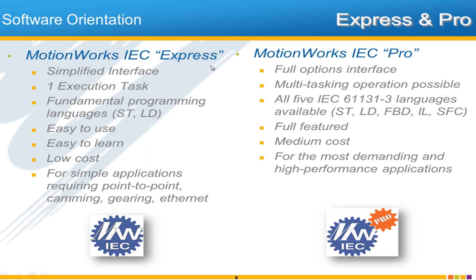The main limitation of Express is that it can only execute one task — we'll see what that means as we progress. With MotionWorks IEC Pro we have multitasking capability, which adds a performance advantage. Express also has the limitation of only two languages: structured text and ladder diagram. Function block code can be inserted in ladder diagram, but with MotionWorks IEC Pro we have full and official access to all five languages.